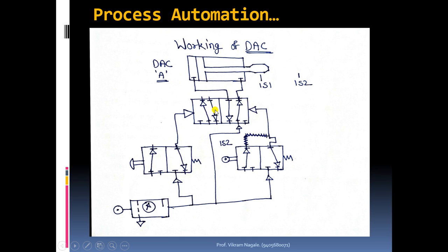And if this is the required condition, there is an additional condition to this. There should not be pressure on the left hand side of this controlling valve. Then and then only, by applying pressure on the right hand side of this valve, we can get retraction. Okay, now this is about the working or controlling of this cylinder by using this 5x2 air operated double sided pneumatic valve.